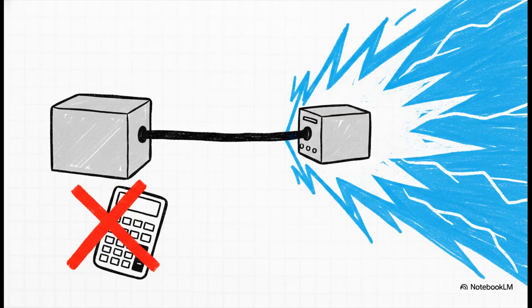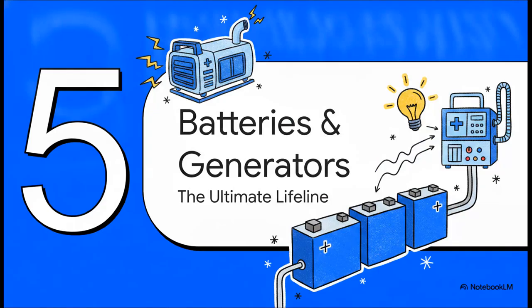And getting them to work in harmony takes actual engineering. You can't just cross your fingers and assume a medical isolation transformer will play nicely with your UPS. When you energize that transformer, the magnetic core creates a massive inrush of current. If you use a generic formula to guess that inrush, you're asking for trouble. You have to verify the transformer's maximum peak inrush current against the specific fault-clearing capabilities of the UPS inverter. If you skip this, someone flips a breaker and you get a catastrophic system-wide trip. Let's move on to Section 5, batteries and backup generators.